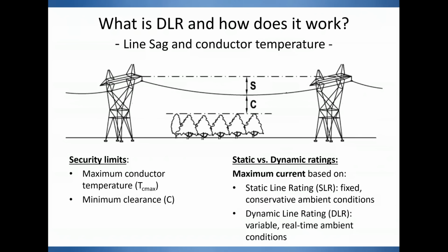Normally, in normal circumstances, most of the grid operators today around the world still use static ratings, which are determined by worst case situations. So basically, we would assume that the line would expand because of the load, that's a Joule effect, and then it would be cooled down by the prevailing weather parameters. And TSOs would typically assume worst case situations, so maximum ambient temperature, no wind speed assumption, high solar radiation, to determine the capacity of the line. DLR, conversely, is trying to achieve that in a dynamic way, hence the name dynamic line rating, by measuring the parameters that impact the capacity of that line in real time.